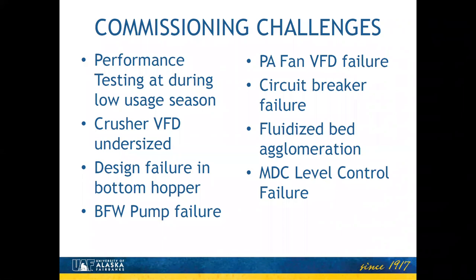Then we had a little cascade of things as we were getting ready to roll. One of the first things we encountered is that the coal crusher is controlled by a variable frequency drive that changes the speed of rotation on that. And we purchased that from another company that packaged it together with the whole coal handling system. And they unfortunately selected the wrong size VFD for it, and it couldn't handle the coal crushing at the rate that we needed. So we were able to work with some electrical suppliers who got us the right size one in relatively short order and got past that and got to the point we were crushing coal.